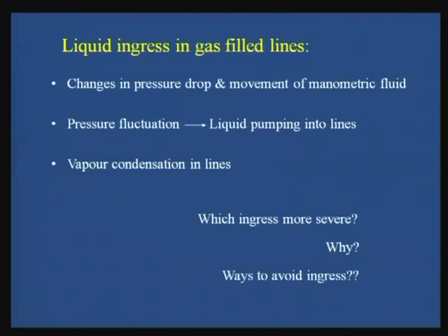Usually there is a tube and we have pressure lines, which may be glass capillaries or glass tapping lines connected to the tubes. In the very beginning I told you how our flow patterns are more or less restricted to a certain number of flow patterns. For air water systems I told you that always the liquid will wet the pipe wall. Do you remember the statement? If liquid has to wet the pipe wall, then due to capillary action, in a gas filled line there will be a greater tendency of the liquid to enter, because it is always trying to wet the pipe wall. So wetting the pipe wall and entering the capillary is much easier in this case. Therefore, liquid ingress in gas filled lines is much more severe and serious, and therefore we usually prefer liquid filled lines.